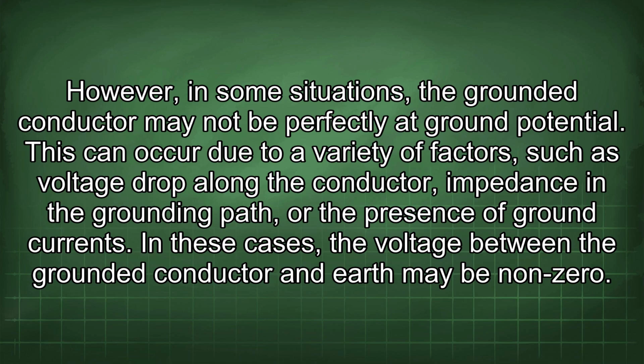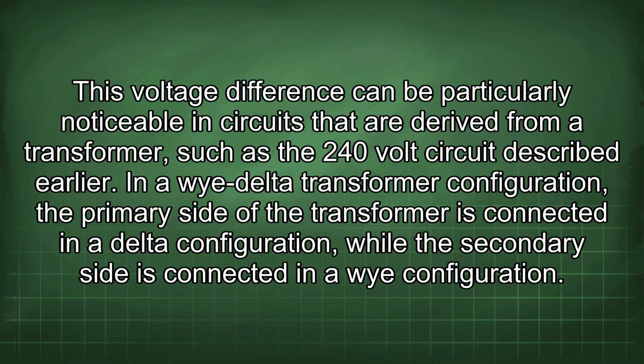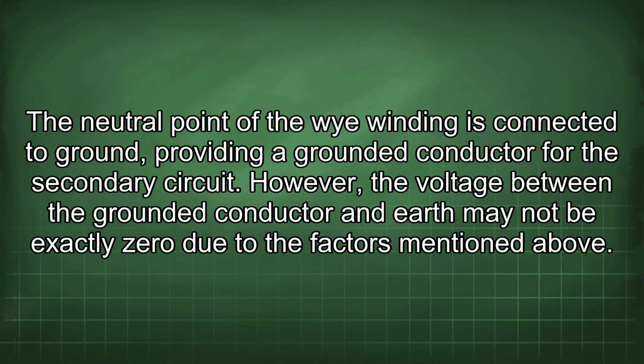However, in some situations, the grounded conductor may not be perfectly at ground potential. This can occur due to a variety of factors, such as voltage drop along the conductor, impedance in the grounding path, or the presence of ground currents. In these cases, the voltage between the grounded conductor and earth may be non-zero. This voltage difference can be particularly noticeable in circuits that are derived from a transformer, such as the 240-volt circuit described earlier. In a wye-delta transformer configuration, the primary side of the transformer is connected in a delta configuration, while the secondary side is connected in a Y configuration. The neutral point of the wye winding is connected to ground, providing a grounded conductor for the secondary circuit. However, the voltage between the grounded conductor and earth may not be exactly zero due to the factors mentioned above.